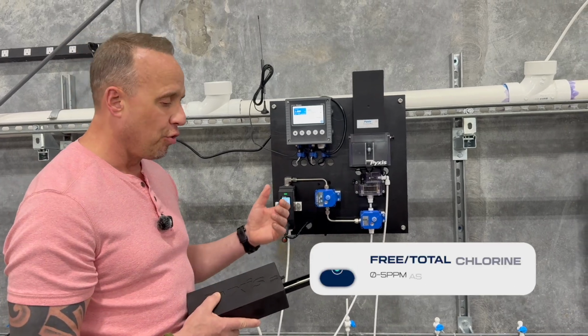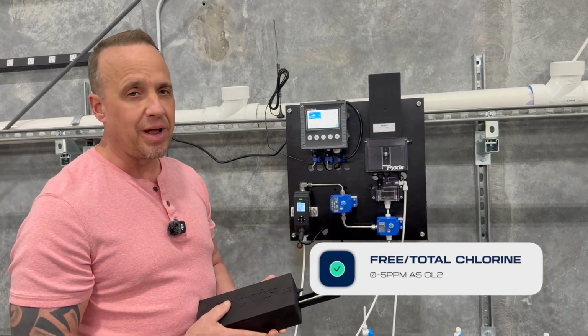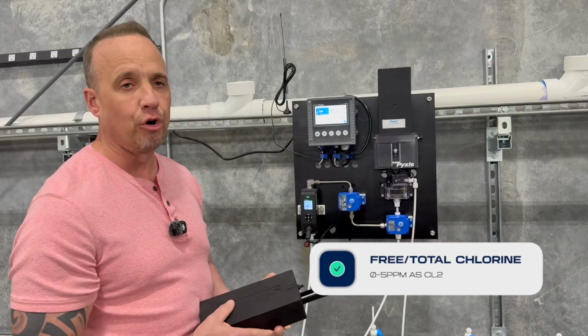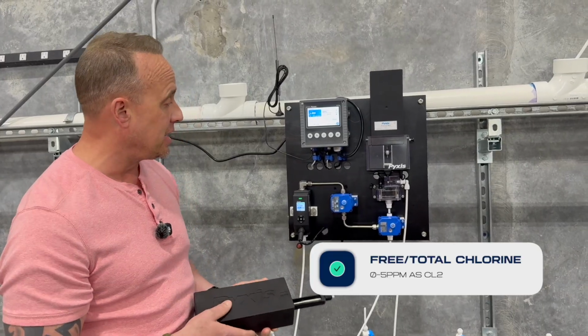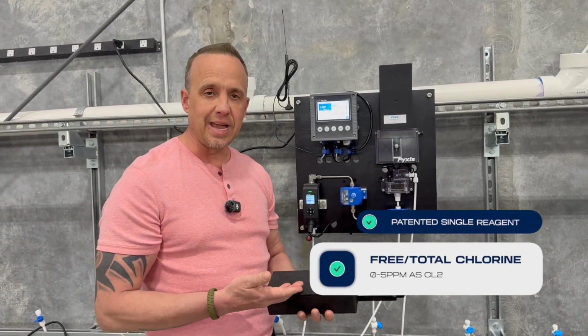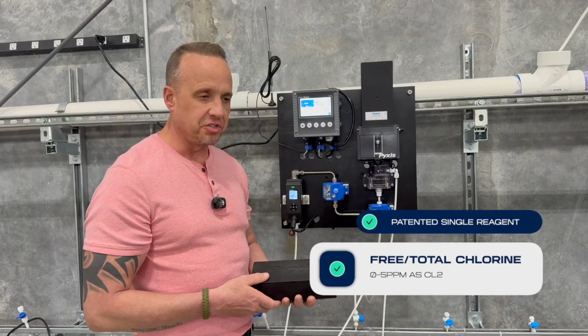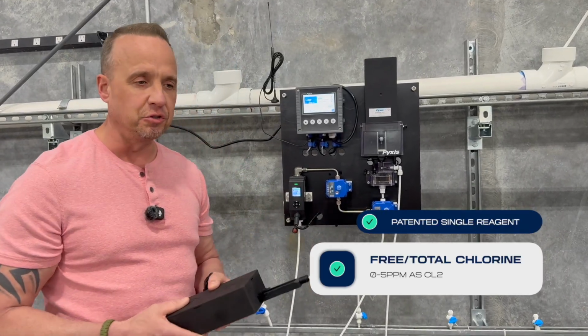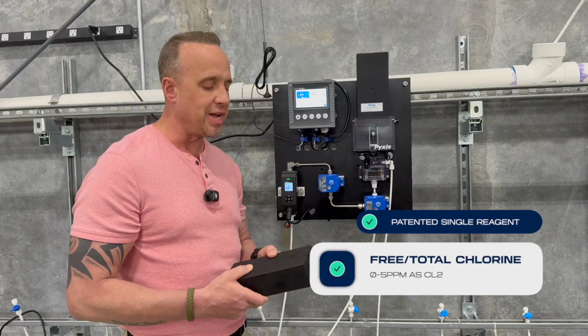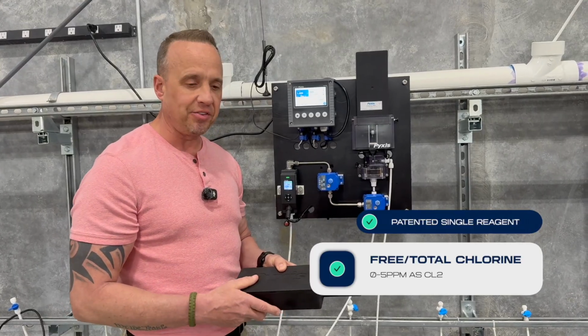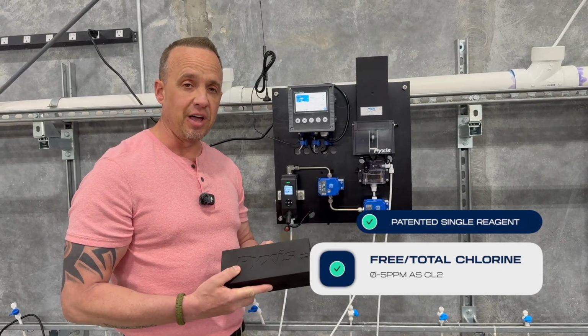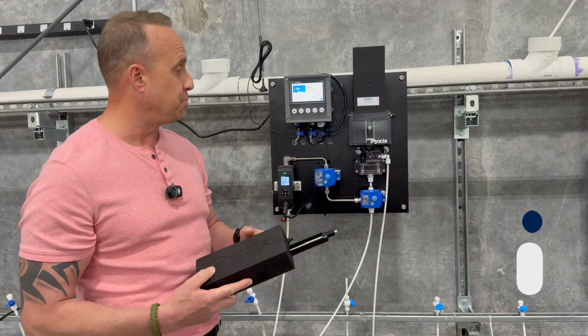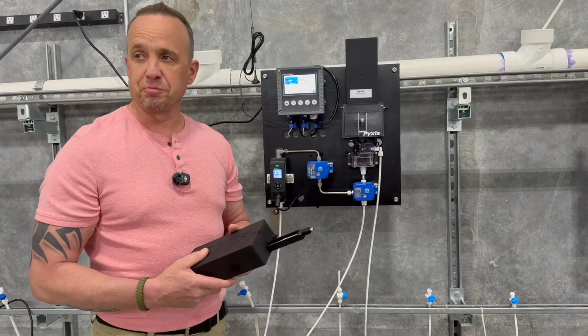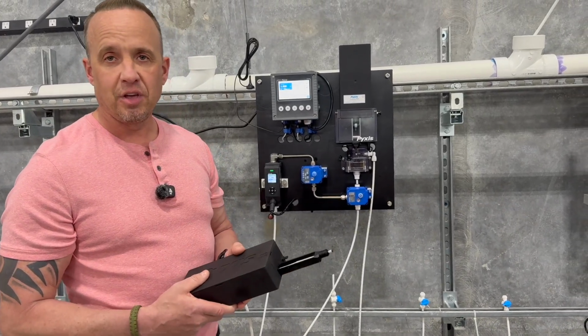We will be offering both free and total DPD wet chemistry version for monitoring chlorine. What makes our version a little bit unique is we have a new patented single reagent version for that test, which doesn't require pre-mixing of buffer solutions or reagent powder with the reagent cartridge. You just snap it in place and you'll get up to 6 months shelf life on that reagent. So you're not disposing the very expensive reagents that you just purchased within 20 to 30 days of installing them.